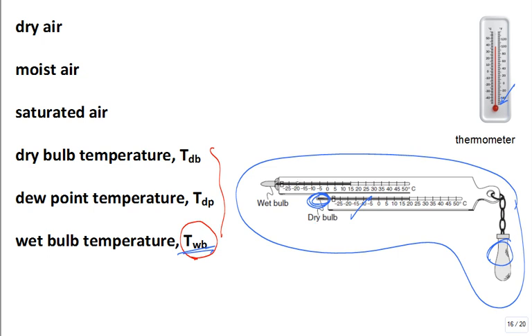Now, think about, first of all, the dry bulb. It's as if I had this thermometer on the wall, right? I had the thermometer on the wall. I then take it off the wall and I start slinging it around in the air. I stop. I look at the thermometer. Did the temperature on the thermometer change because I was slinging it around in the air? No, it didn't. That's a big conclusion. Some people will say, well, if it's cold air and I'm slinging it around, won't it feel colder? You're confusing the person who wants to stay at a constant body temperature and now the body has to work harder to stay at that constant temperature when it's really cold outside and the wind is blowing. That's wind chill. But if the thermometer doesn't care, it just says, I'll measure the temperature and report it to you. It's not trying to stay warm. And so when you sling it around, the dry bulb temperature will stay the same. What you will measure on that thermometer that's not covered with any moisture is the dry bulb temperature of the room. But they have another thermometer and they put a little cloth surface on it. It's a little wicking material. And they get it wet and they have a little reservoir, not much of a reservoir, to keep it wet.